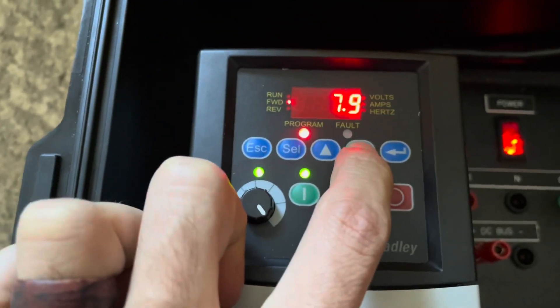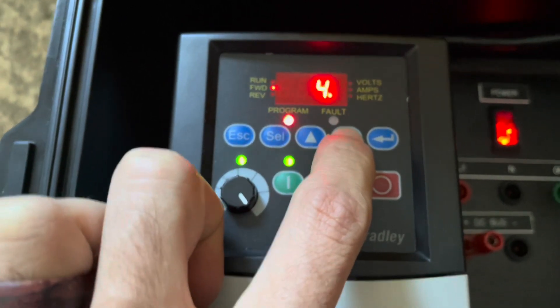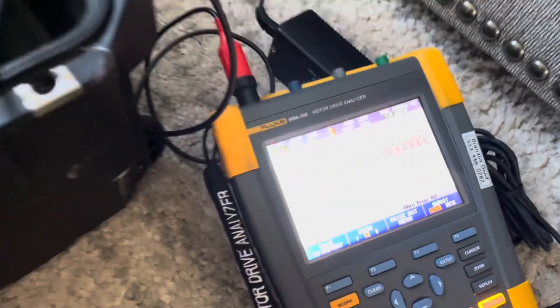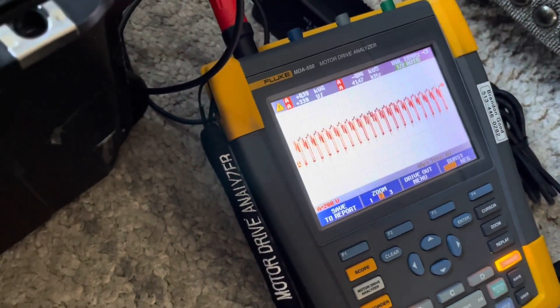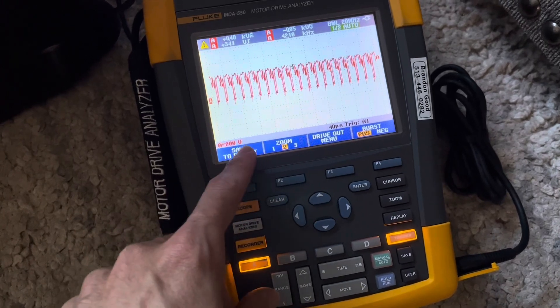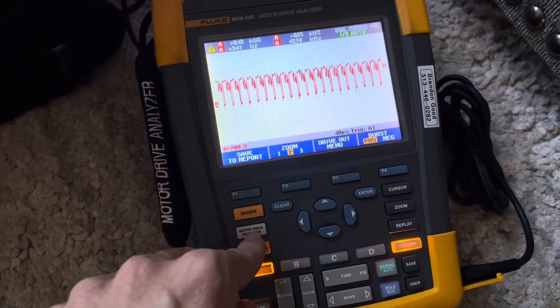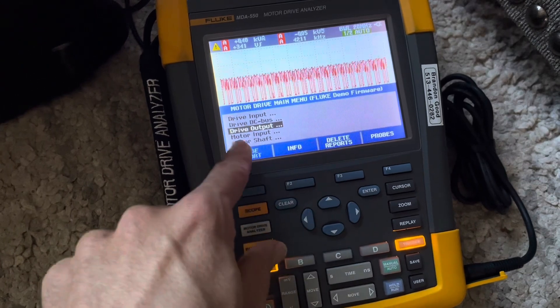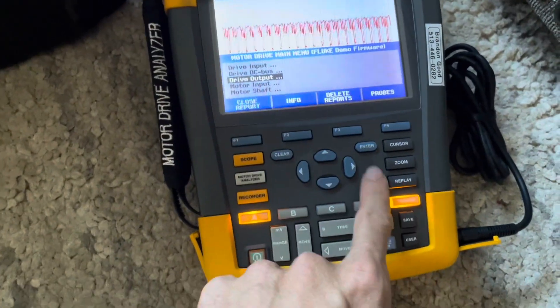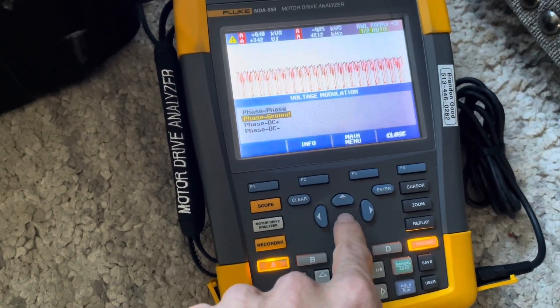We're going to take it to the default of 4 kilohertz, run the VFD, and show you how to measure it on the motor drive analyzer. To measure pulse width modulation frequency or carrier frequency, click 'Motor Drive Analyzer' mode, then navigate up and down to select 'Drive Output,' hit Enter, then select 'Voltage Modulation' and hit Enter.